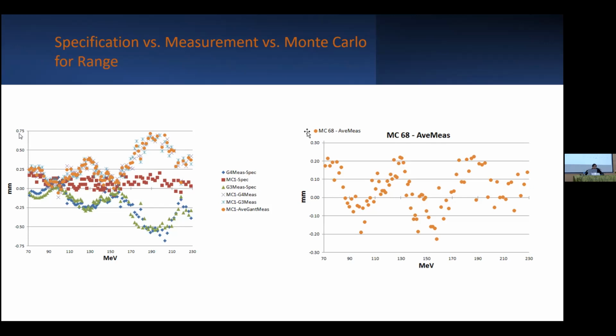So what I'm showing here is basically, if what the vendor said in their specifications were exactly true, we would have gotten this to all be 0. But there was variation, and you see this wave pattern, and this is up to, over here, a quarter millimeter. The difference between two different gantries, this was one gantry and the other, they were actually exactly opposite of each other. If you just took a standard average, you could have been off by maybe up to 1 millimeter. So this is because of all the characteristics of everything that comes through at the end. What really matters is the physical measurement you make, and that's why it has to be very precise. Because again, that's the thing that goes into the software that then does the calculation that's going to be used to treat the patient.